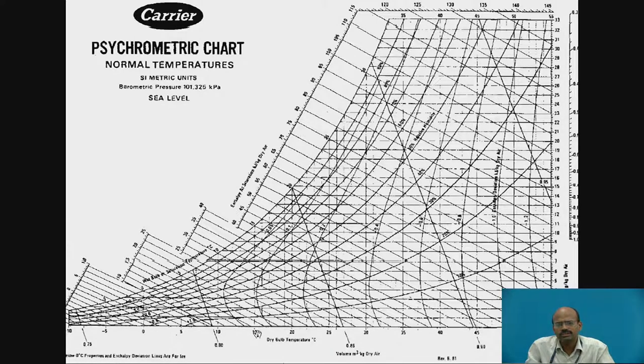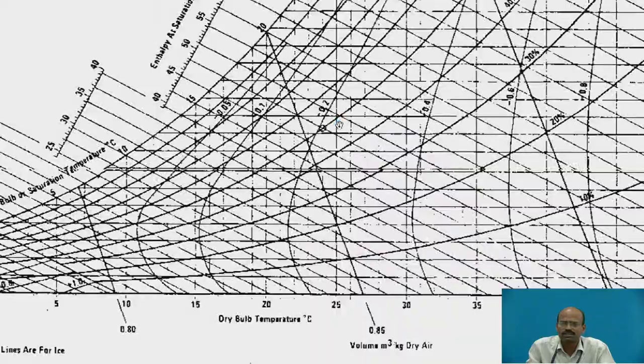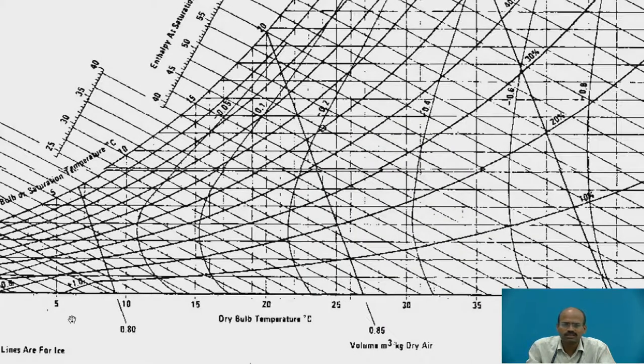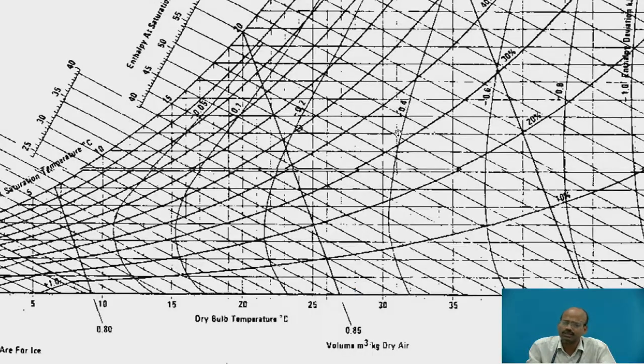Here along the x-axis, dry bulb temperature scale is taken. The temperature for this carrier chart starts from minus 10 degrees Celsius to plus 55 degrees Celsius. For DBT lines, I have to take vertical projection, parallel lines to the y-axis. These lines will be constant DBT lines. For example, this is 25 degrees Celsius line, this is 20 degrees Celsius line, this is 30 degrees Celsius line. We can measure the DBT temperature by using simple thermometer of moist air and those temperatures we can locate along these DBT lines.